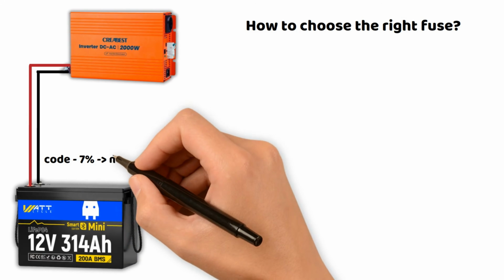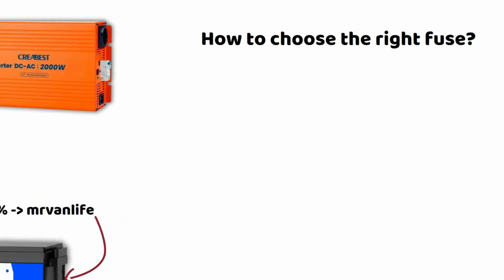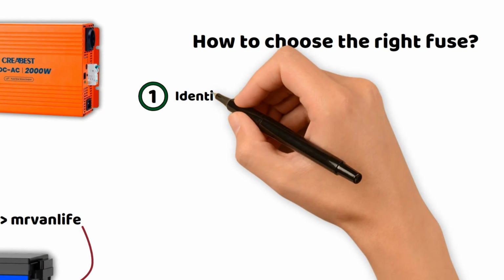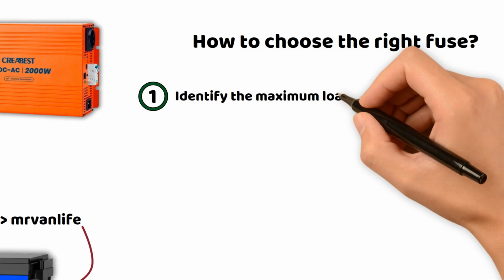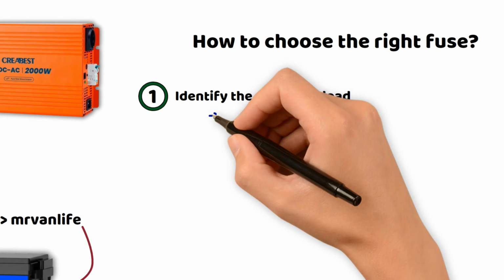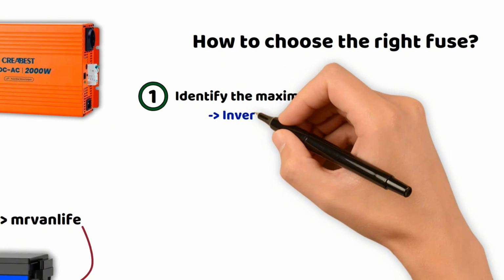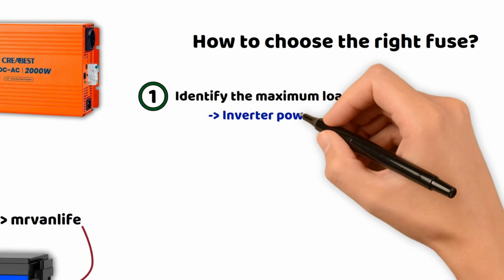Step 1. Identify the maximum load. The device with the highest consumption here will be the inverter, which has a power of 2000 watts when subjected to a load of that value. Here, we are going to size our setup based on the maximum power of the inverter.